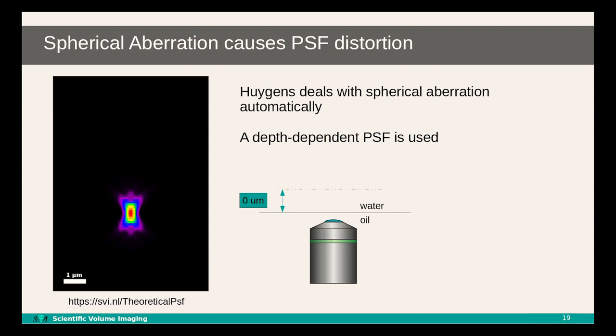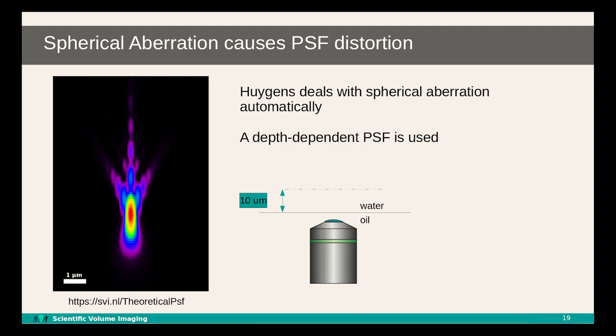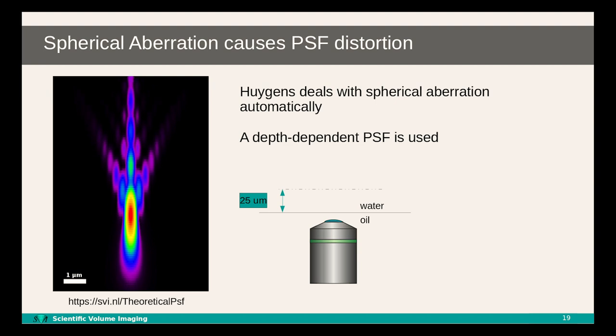Another important issue that is very often neglected in microscopy image restoration is spherical aberration. Spherical aberration is caused by a refractive index mismatch between the lens medium and the sample medium. The deeper you image in your sample, the more elongated and asymmetrical the PSF becomes, causing your objects to distort the deeper you image. Huygens can calculate the spherical aberration effect automatically and will correct for it, provided you set the refractive index settings in the Huygens parameters correctly.